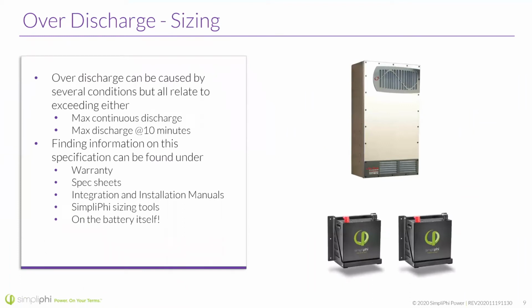Over discharge can be caused by several conditions, but all relate to exceeding either max continuous discharge or max discharge at 10 minutes. Those are specs found on the battery. If you're looking at our 3.8 kilowatt hour battery, you can assume 37.5 amps DC per battery is the max continuous discharge, and the max discharge at 10 minutes is 80 amps DC per battery. So regardless of how it happens, something has to happen here.